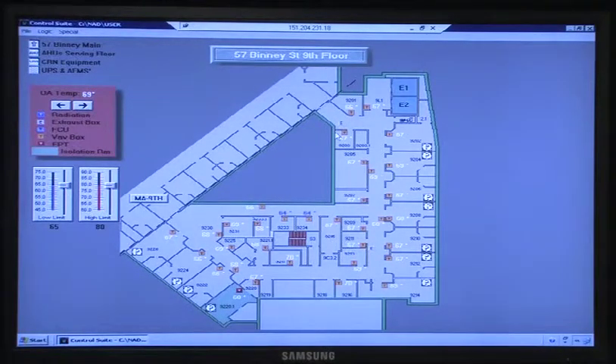It's just showing the multiple relationship, where there are multiple supply boxes married up to the same one. They're exhaust, actually. What you consider, they're return boxes. I'm sorry, return boxes. Throw another curve, Jamie, and put an R in there instead of an E. Oh, exhaust box. Okay. It's exhaust, but it's really a return box. It's return boxes, not exhaust fans or exhaust boxes. Those are returns. Okay? And they're tracking supply. We don't exhaust.